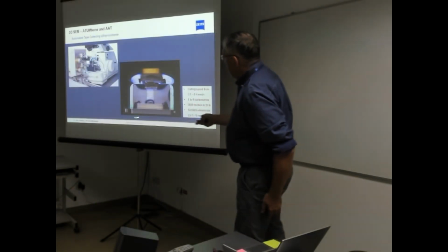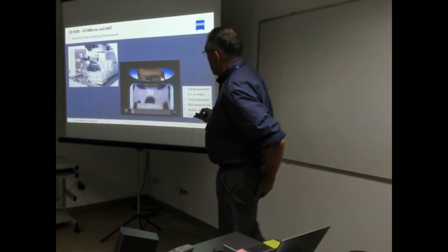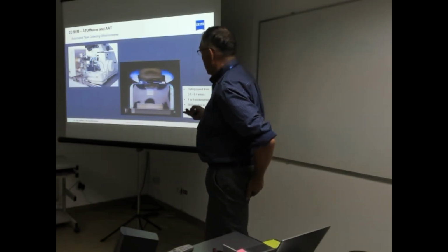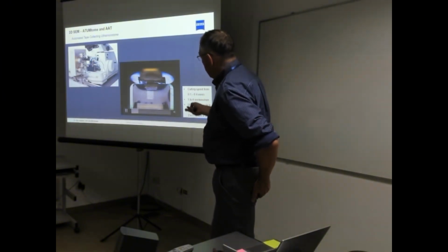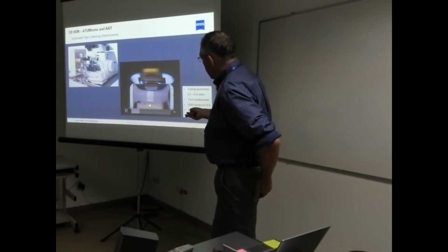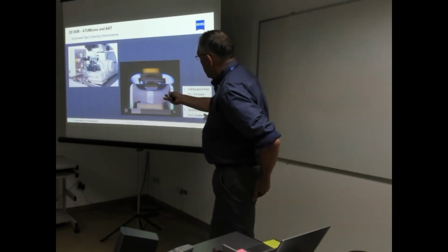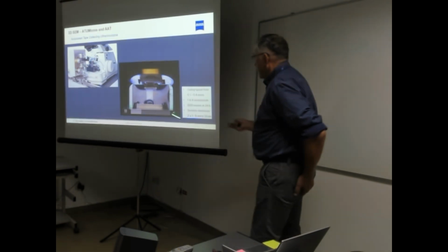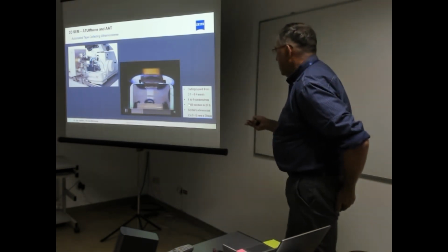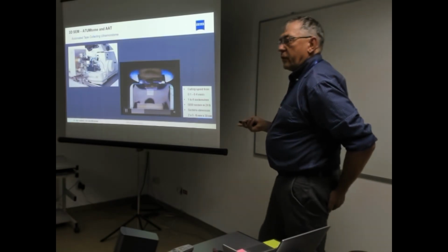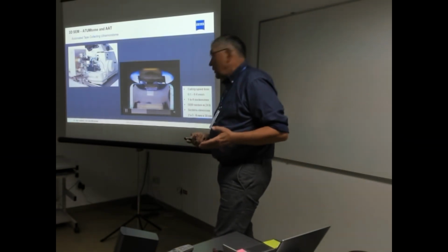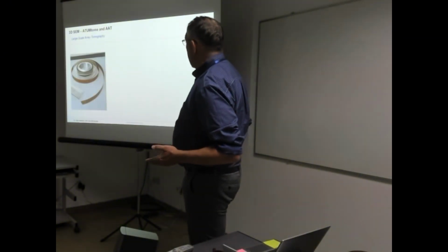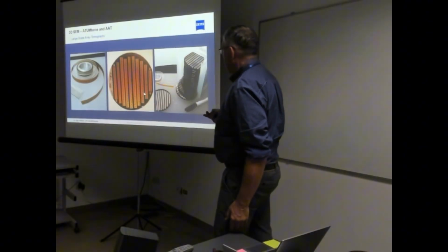What you see here is the activity of this automated ultramicrotome. This is the tape surface. This is the section which comes from the knife blade. Now it's taken up by this tape, and this operates totally automated. You can create something like 5,000 sections a day. Then you have a lot of material to image, which represents the 3D volume in the end. This tape has to be cut into sections.